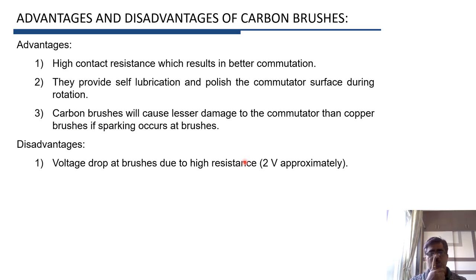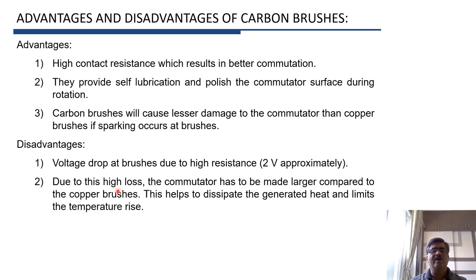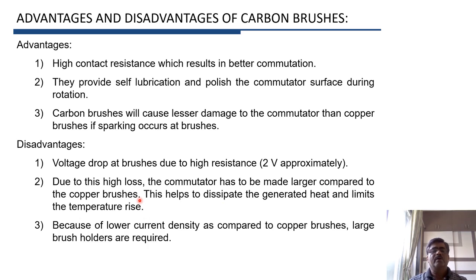However, there are some disadvantages. The main disadvantage is that due to the high resistance of carbon brushes there will be a voltage drop at the brushes, approximately of the order of 2 volts. Another disadvantage is that because of this high loss, we have to increase the size of the commutator to dissipate the generated heat and keep the temperature rise within permissible limits. Also, the current density of carbon brushes is lower compared to copper brushes, so the brush size and brush holders are also larger.